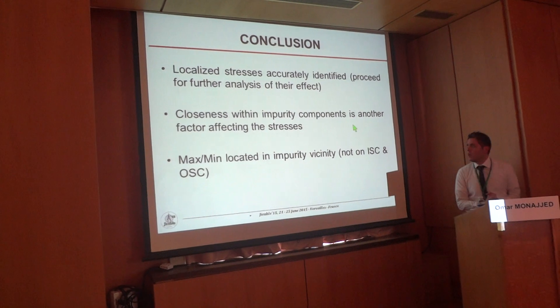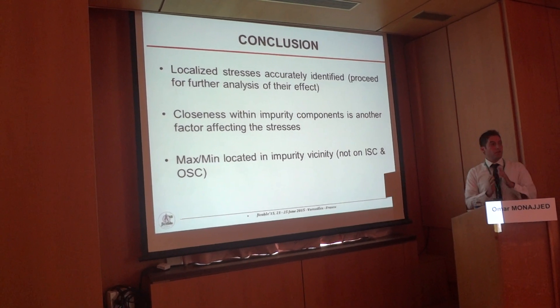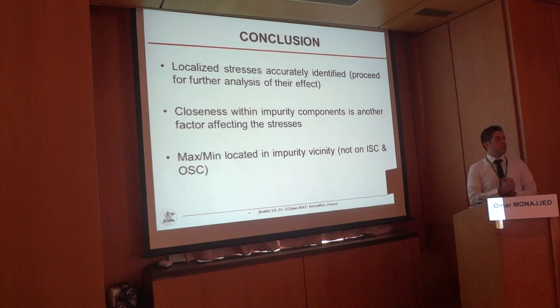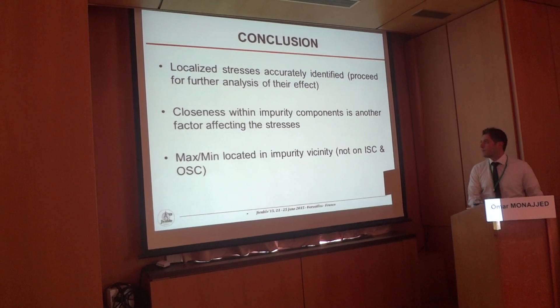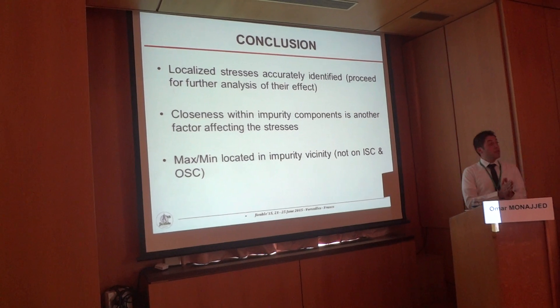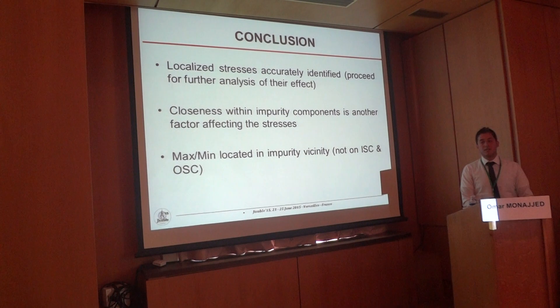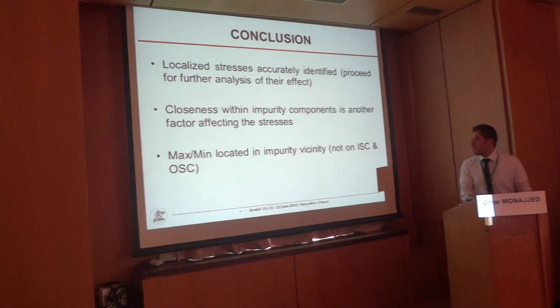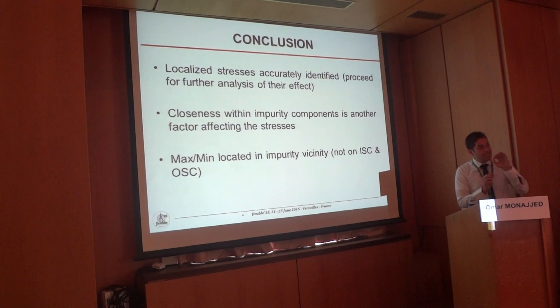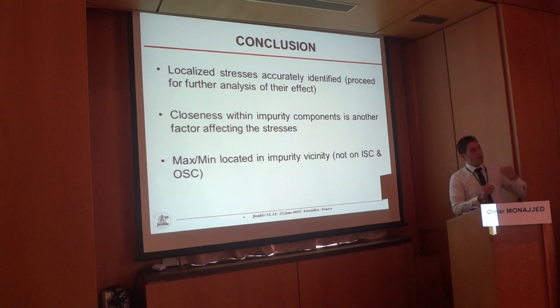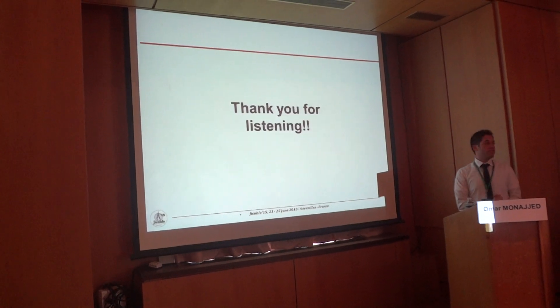For the conclusion: localized stresses have been accurately identified, so now we can proceed to further analyze the effect on insulation performance, like partial discharge, water treeing, and so on. Next, closeness between impurity components is another factor — the closer they are, the higher the stresses. Third and finally, maximum and minimum stresses are located in the vicinity of the impurity, and not on the inner semi-con and outer semi-con. Thank you for listening.